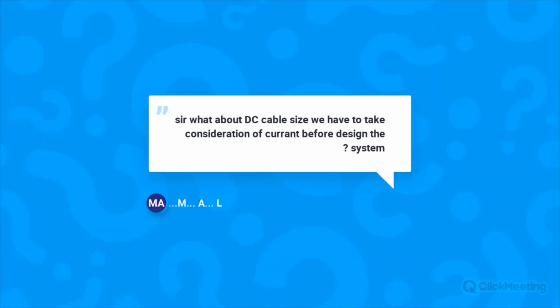Okay, so let's move on to the next. There's another question: what about DC cable size? We have to take current into consideration before designing the system. Yes, definitely. That's why, in most of what we try to explain, we say the system parameters are predetermined in design. So in the design stage, you already know what your maximum current will be, what your maximum voltage will be, your VOC, and all those parameters. So you are able to amply size the DC cable that can match that system design. So, next question, if there's any.